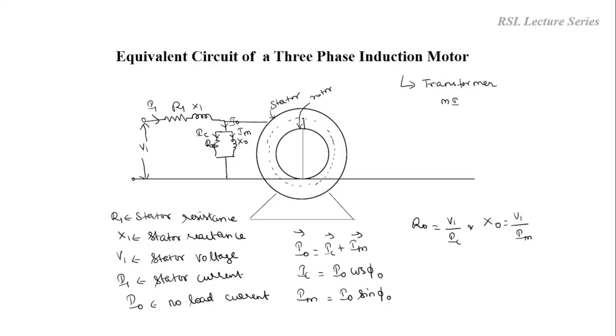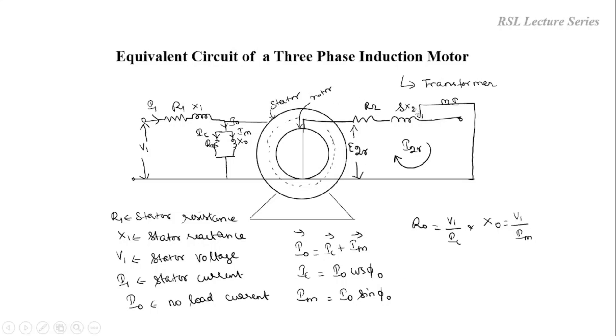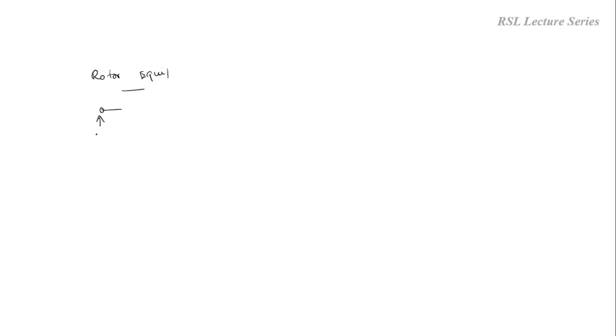Similarly on the rotor side, we can draw the rotor resistance R2 and the rotor reactance, represented as S times X2 under running condition. These are the per-phase values. E2R is the EMF induced in the rotor under running condition, and I2R is the current flowing through the rotor under running condition. These are all the components on the rotor side. We will now draw the rotor equivalent circuit separately. E2R is the EMF induced during running condition, R2 is the rotor resistance per phase, and SX2 is the rotor reactance under running condition, which is a variable. I2R is the current flowing through the rotor.